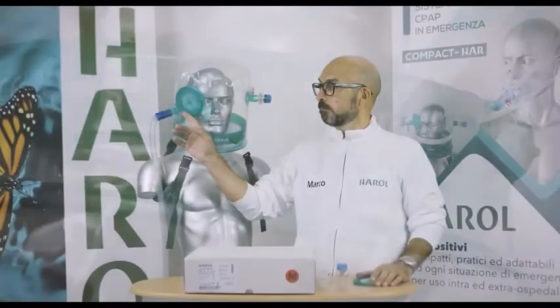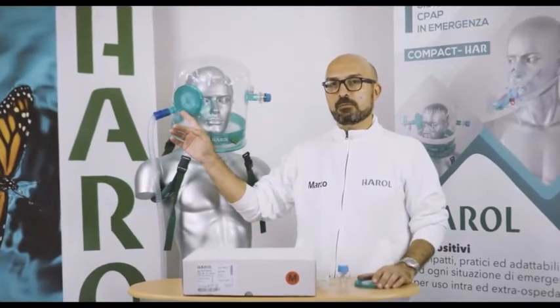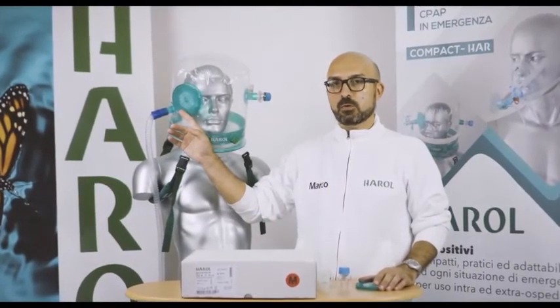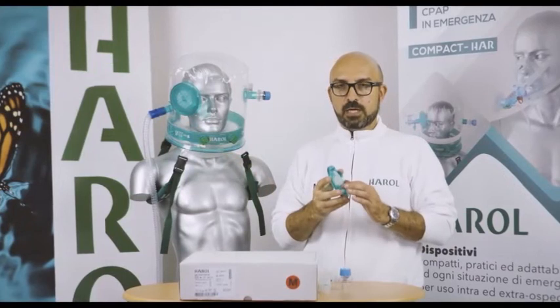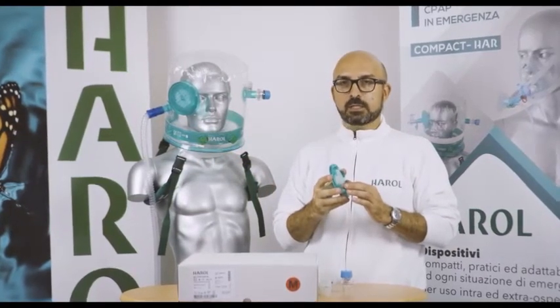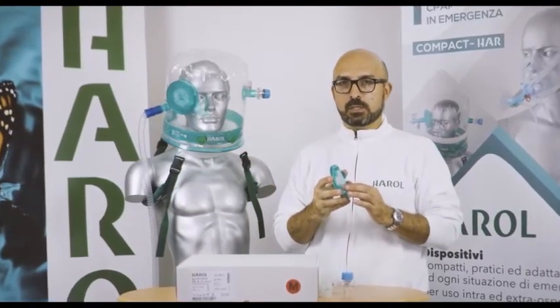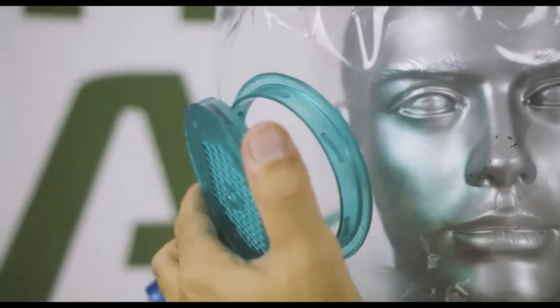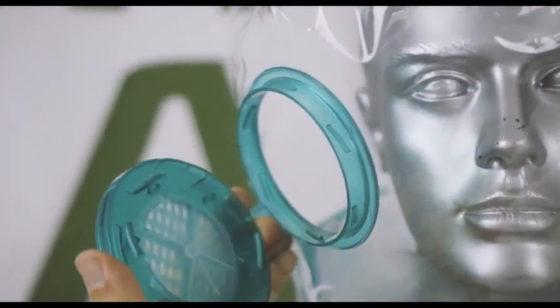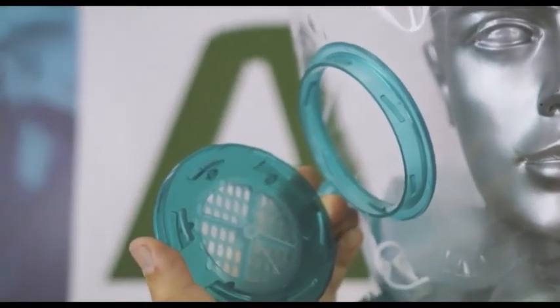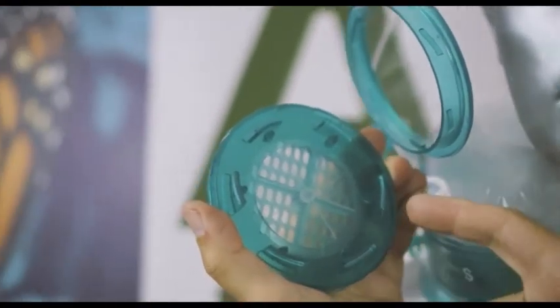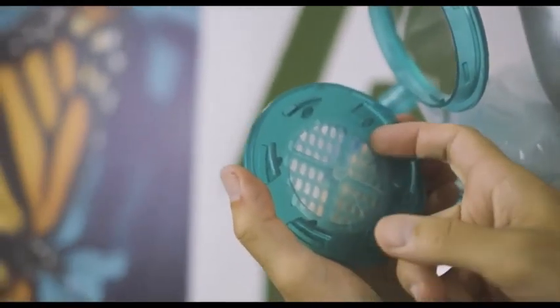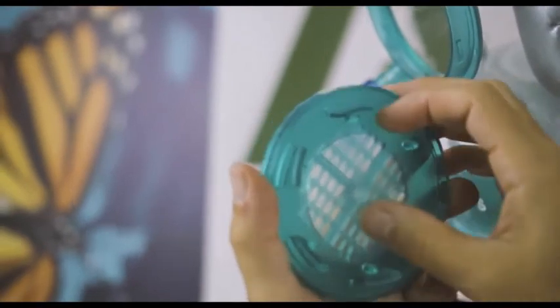The Harol helmet is equipped with a side access port, which allows routine operations to be performed during therapy, without the need to remove the entire helmet. On the access port is placed a bidirectional anti-asphyxia valve. This valve automatically closes when the helmet pressurizes, and opens automatically when the pressure inside the helmet falls below 2 centimeters of water, without any operator's intervention.